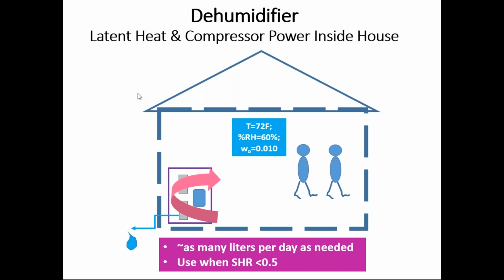Finally, I'll mention the dehumidifier, and you can get as many liters per day capacity, whether it's a basement dehum like you'd buy in a big box store for a couple hundred dollars, or an inline ducted high quality dehumidifier. You'll find that these can operate below a sensible heat ratio of 0.5. That is, they can operate with a load that's dominated by latent. And what's interesting about this is that because the unit is contained within the house, the heat that's pulled out of the water to condense the water vapor and the compressor power that's put in for driving it is released as heat inside the house, which increases the sensible cooling load of your air conditioner. And so it's actually a nice match with an air conditioner when you have excessive dehumidification conditions that need to be managed. It bumps up the sensible heat ratio for your standard air conditioner while getting rid of moisture that the air conditioner cannot remove.